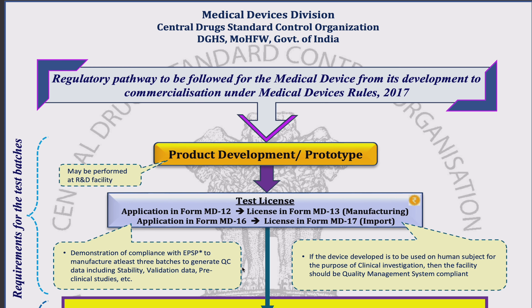I am going to focus on the regulatory pathway as per the Indian CDSCO. The regulatory pathway is mainly divided into three phases for a particular product. The first phase is the requirement to manufacture test batches. The second phase is to conduct a clinical investigation study on investigational medical devices if applicable. The third phase is the commercialization phase.